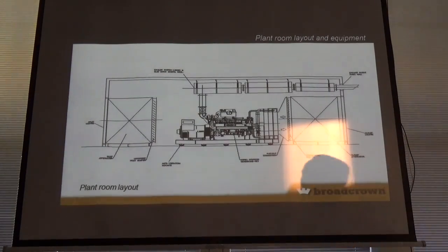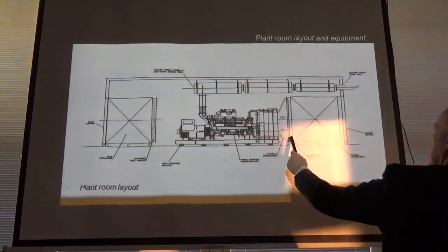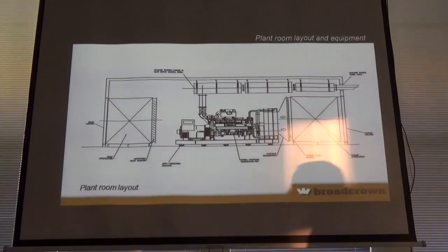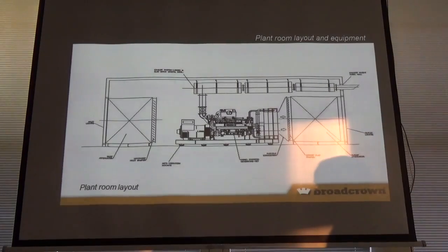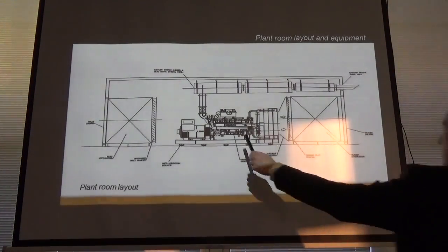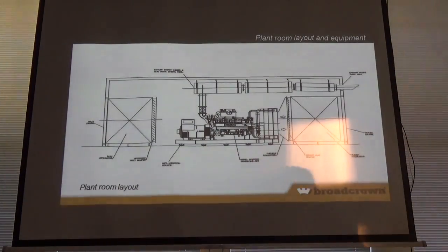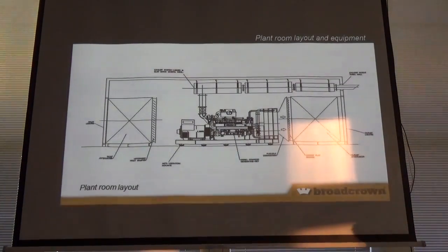So the reason why there's a damper here and there's a damper there is your diesel generator is basically sitting there in anticipation of needing to start. It's got jacket heaters there on the unit that are constantly running and topping up, basically thermostatically controlled. Now when that set's running, it's probably 80s return temperature to the engine block, okay, early 80s. What basically happens with the standby rated unit is the thermostatically controlled heaters will probably maintain temperature of the cooling system to about halfway house, 40-45 degrees centigrade, because it's wanting that set to be ready and to take the most load acceptance and be up to running and cracking along.